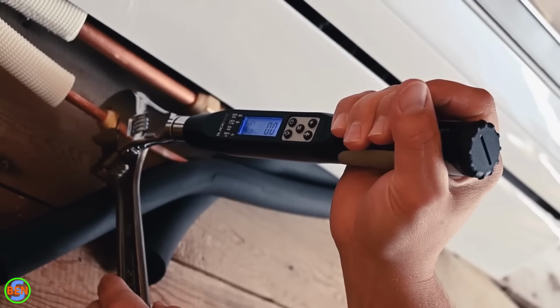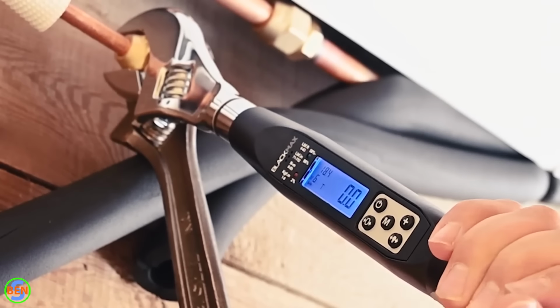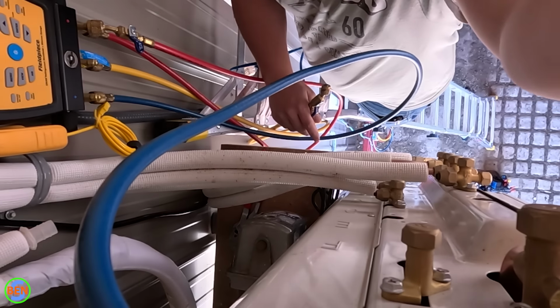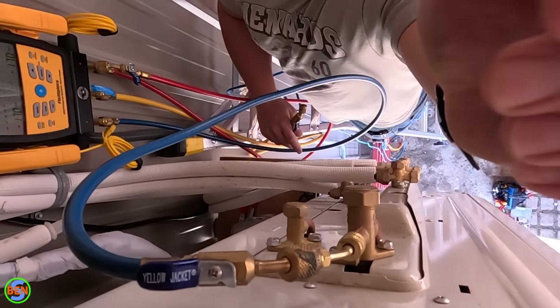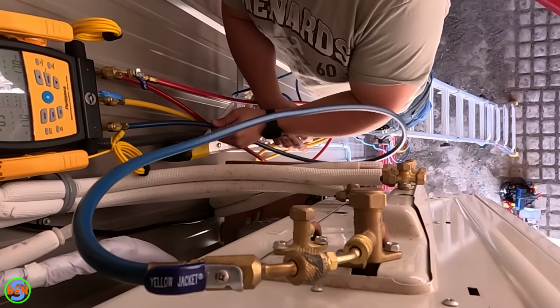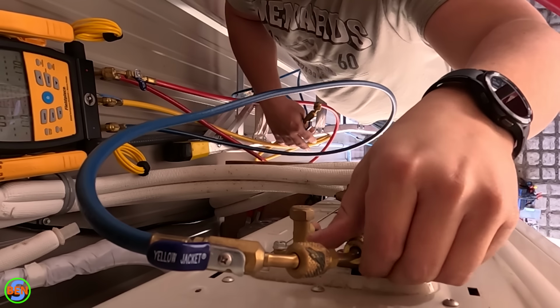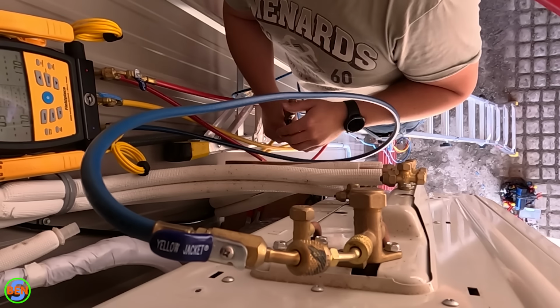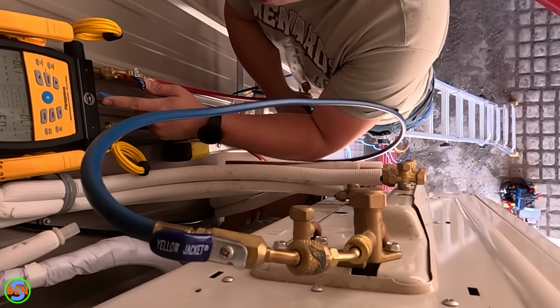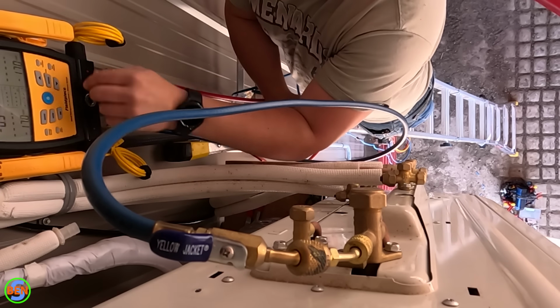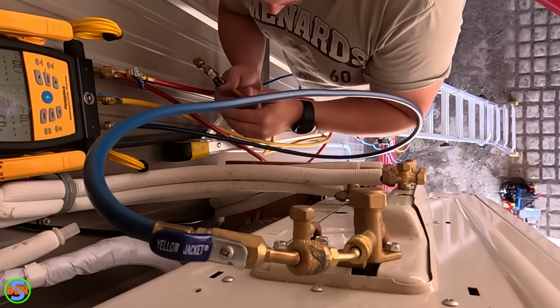So repeat that process as many times as necessary until you have all of your line sets connected, and then we are ready to move on to pulling the vacuum on the system. Now for this particular unit, it was really nice the way this one is designed. We can just pull the vacuum on a single port on this outside unit. We don't actually have to pull a separate vacuum on each line set individually.